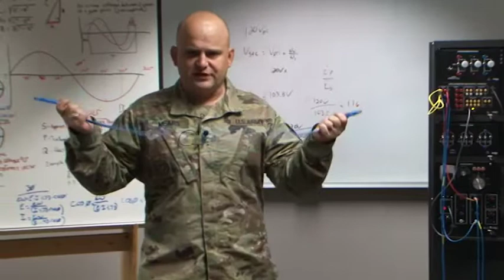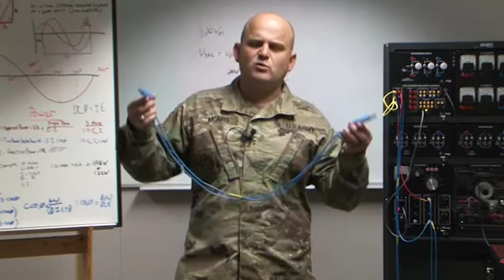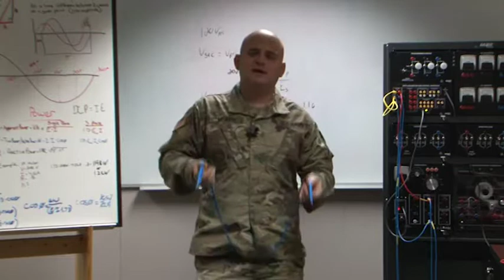How does that apply to transformers? The same applies. It goes back to ampacity, because one principal way to calculate power is P equals IE. In parallel, whether single phase or three phase, we'll have similar voltages. But if we add more conductive material, more transformers in parallel, we're increasing the power capability of those transformers on the output side.